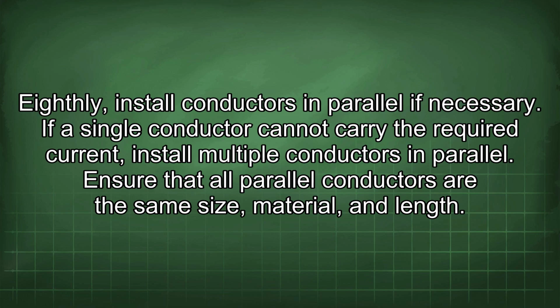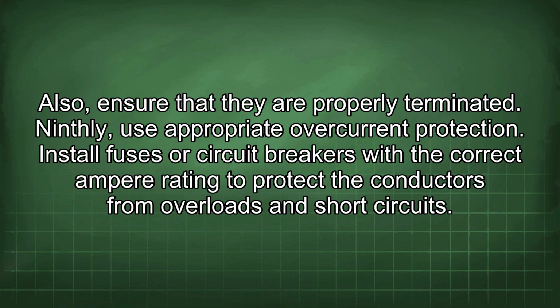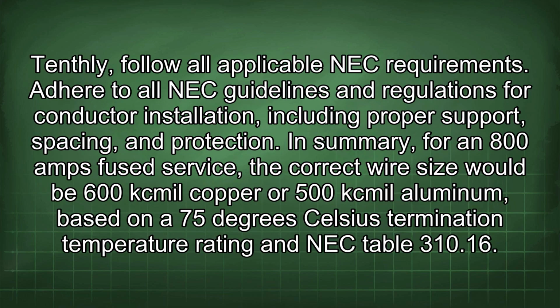Eighthly, install conductors in parallel if necessary. If a single conductor cannot carry the required current, install multiple conductors in parallel. Ensure that all parallel conductors are the same size, material, and length. Also, ensure that they are properly terminated. Ninthly, use appropriate overcurrent protection. Install fuses or circuit breakers with the correct ampere rating to protect the conductors from overloads and short circuit. Tenthly, follow all applicable NEC requirements. Adhere to all NEC guidelines and regulations for conductor installation, including proper support, spacing, and protection.